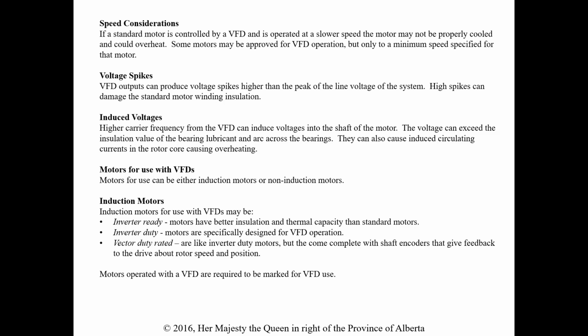Motors for use: the motors we can use can be induction motors or non-induction. The induction motors I talk about are inverter ready. They have better insulation and thermal capacity, so the heating's not such an issue. Inverter duty motors are specifically designed for VFD operation. And vector duty rated motors are like inverter duty motors, but they come complete with shaft encoders to give feedback to the drive about rotor speed and position. So these would be very specific and I assume quite expensive, in that you can send a signal back to a computer or PLC or something that's telling the system exactly how fast the motor is going, and then it can make adjustments based on that.